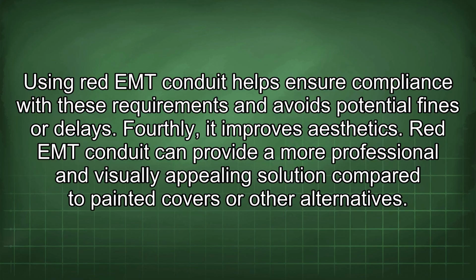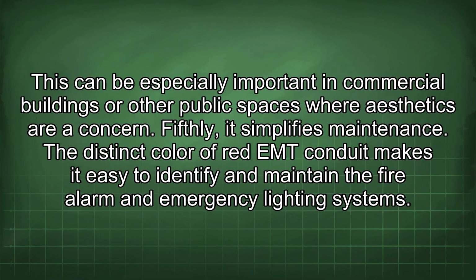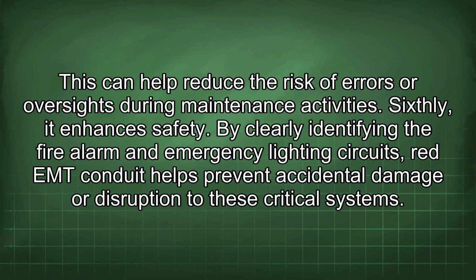Fourthly, it improves aesthetics. Red EMT conduit can provide a more professional and visually appealing solution compared to painted covers or other alternatives. This can be especially important in commercial buildings or other public spaces where aesthetics are a concern. Fifthly, it simplifies maintenance. The distinct color of red EMT conduit makes it easy to identify and maintain the fire alarm and emergency lighting systems. This can help reduce the risk of errors or oversights during maintenance activities.